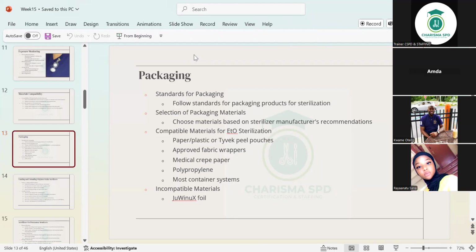That is what I was telling you yesterday, that even in this low temperature sterilization, you're going to position them in the sterilizer like books in the library, in the bookshelf. The paper side and then the plastic side. So the paper side of the next one is going to come next to the plastic side of the other one. That's how you arrange it, in the same order, so that you don't put two plastic sides facing each other. No, the paper side must face the plastic side of the other pouch, in the bookshelf style. Alrighty, that's just a reminder.